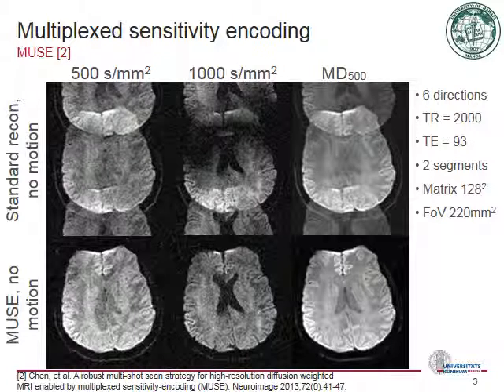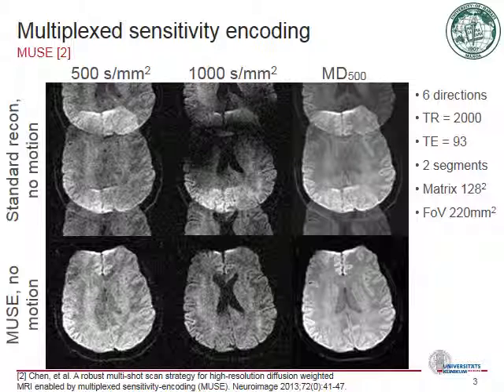Even with prospective motion correction, phase differences due to diffusion weighting gradients can lead to substantial ghosting artifacts in multi-shot DWI, as shown in the upper row. The MUSE algorithm makes it possible to determine the phase of each k-space-based segment. The phases are then included using the coil sensitivities, leading to artifact-free images in the final reconstruction, as shown in the lower row.